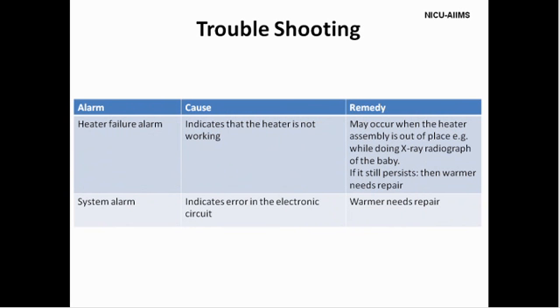When the heater is rotated to the side position, for example while doing an X-ray, the heater is switched off and the heat off indicator is switched on. The audible heat off alarm activates after 5 minutes if the heater is not returned to the normal position. This alarm can be silenced by pressing the alarm silence switch, which will bring back the heater to its normal position. System alarm indicates that there is an error in the circuit and it mandates the need of repair of the radiant warmer.